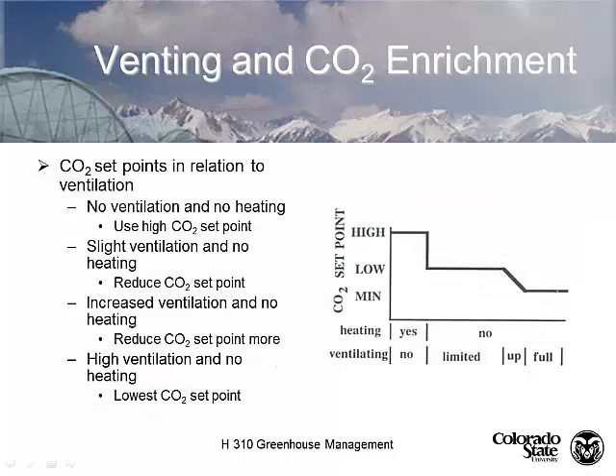Between 10 and 20 degrees centigrade is optimum for most crops, though it's very crop specific. We'll program our step controller with set points based on whether heating is on or not, because if ventilation is on and we're exhausting the greenhouse, we don't want to inject CO2 and pump it right back out of the atmosphere — we paid for it.